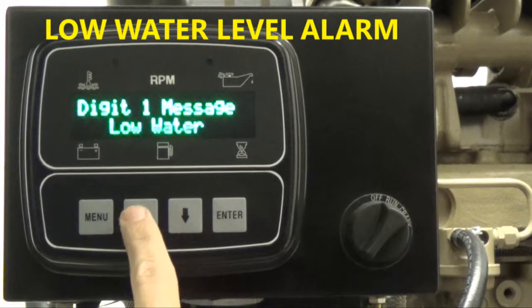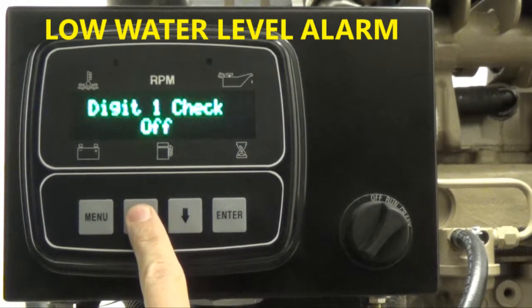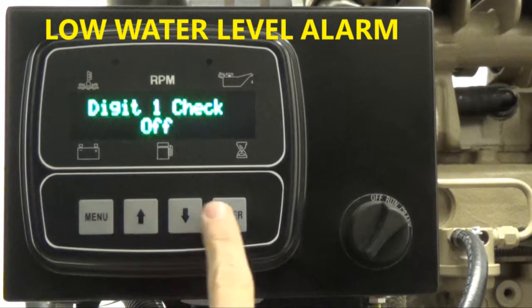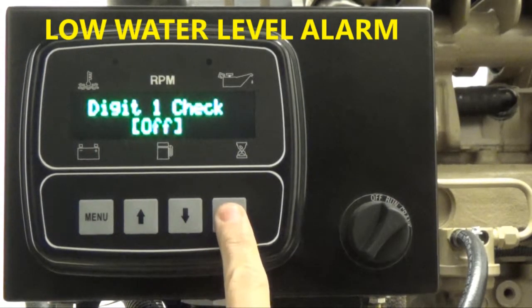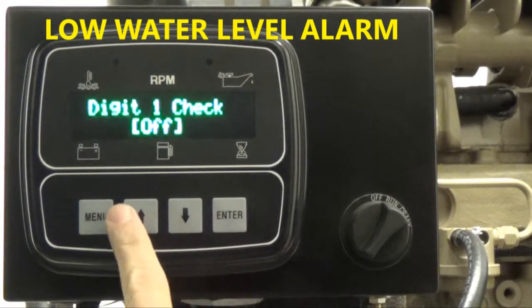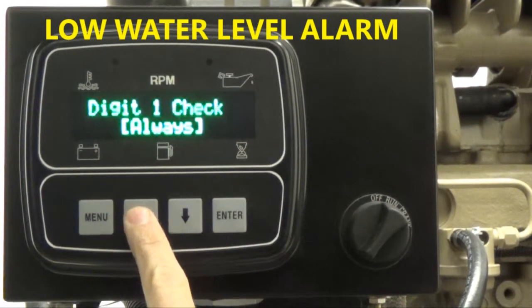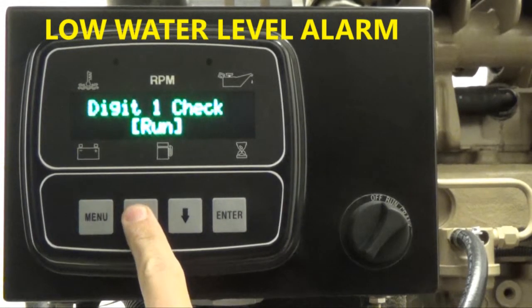Press the up arrow button to view the current digital 1 engine check setting. In this video, because we are assigning an alarm action to the digital input, you would want to adjust the setting from off to run. To do so, press enter and brackets will appear around the current setting. Keep pressing the up arrow button until you reach run. This means that it is necessary for the controller to pay attention to the alarm settings only when the engine is running above 450 RPM, also allowing for a bypass time delay. It would not be necessary to check for the alarm when the engine is not running and is turned off. Then press enter to remove the brackets.